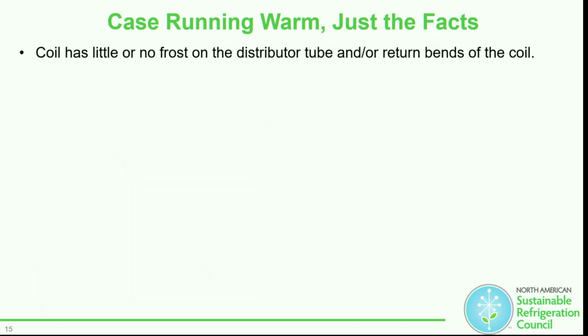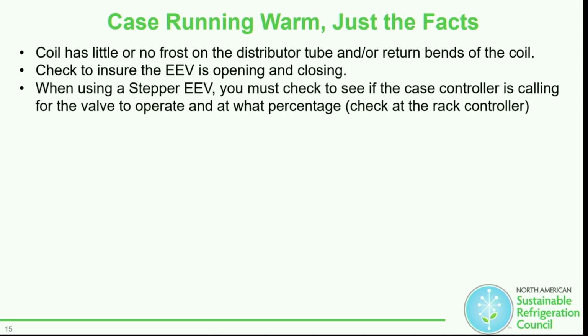If the coil has little or no frost in the distributor tube, and/or the return bends of the coil, check to ensure the EEV is opening up. Now we're talking about pulse or bipolar steppers. When using a stepper EEV, you must check to see if the case controller is calling for the valve to operate and what percentage the valve is at. You can check at the rack controller, but preferably you want to do it right at the case controller if it has a display, because like I stated before, a lot of times there is a delay between what the rack controller is showing and what the controller locally is going to show you.